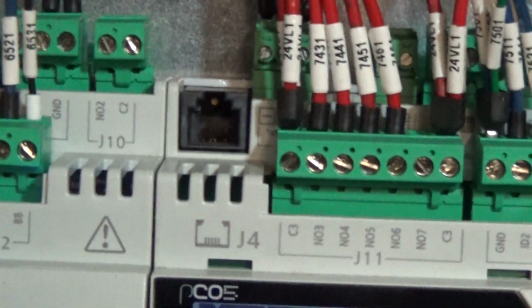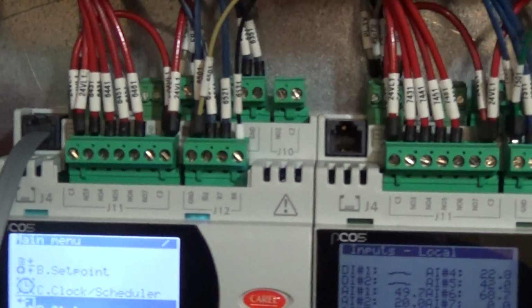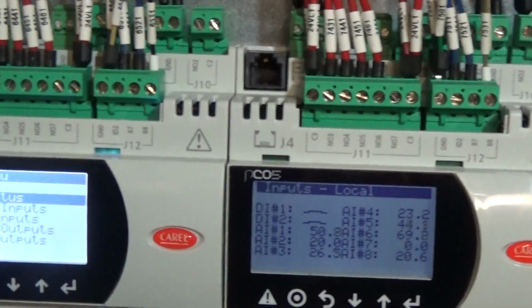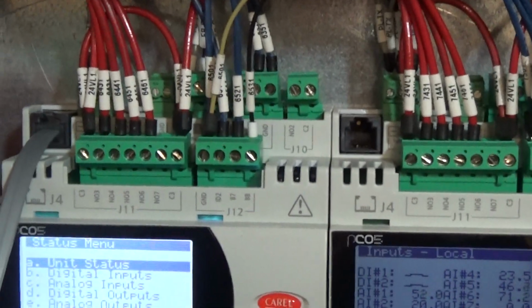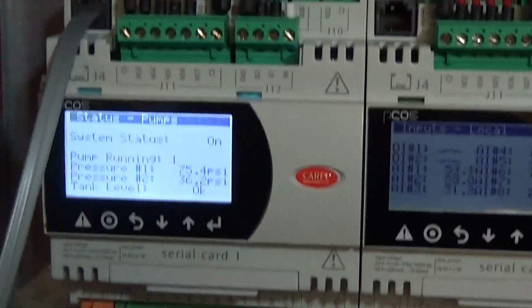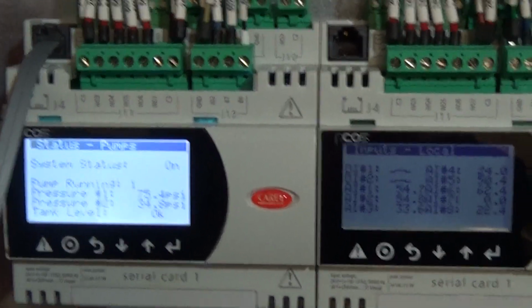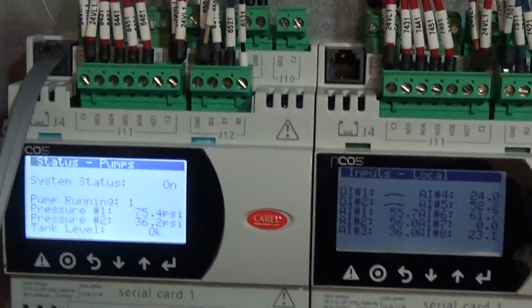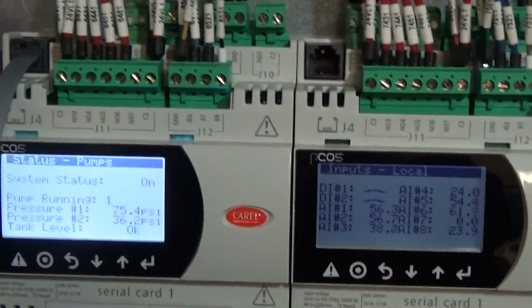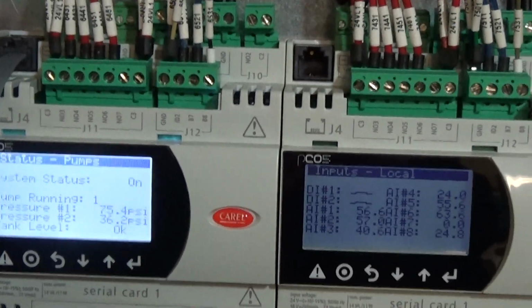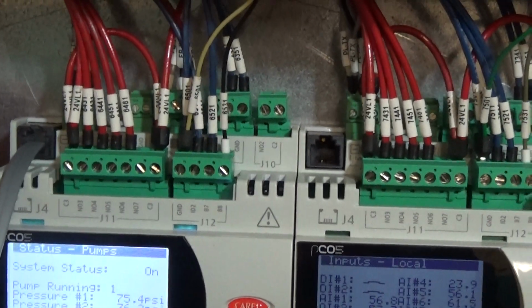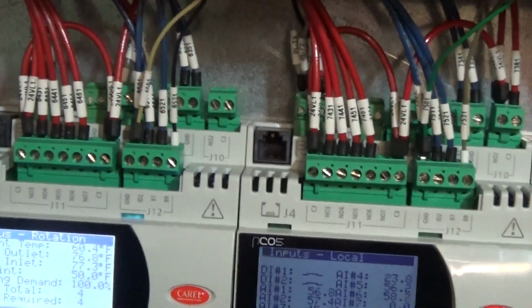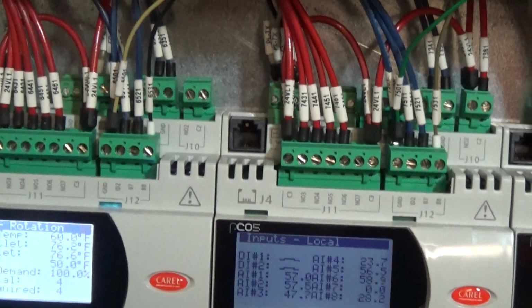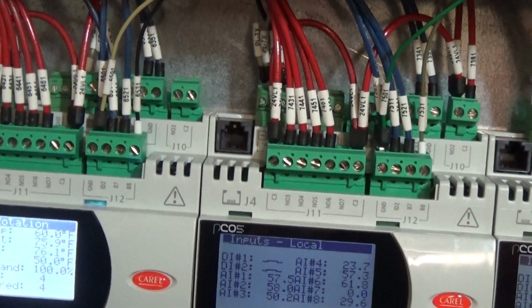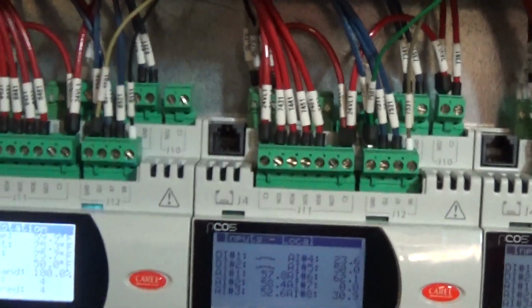And the nice thing about the PLC here is it gives me a status screen that I can read the different fluid pressures and refrigerant pressures and temperatures in the whole machine. So I'm in the status menu, I'm highlighted on unit status, I can hit enter. And what it shows me is pump 1 is running. The pressure on the flow control valve inlet is 75 psi, and the transducer on the other side is sensing 36 psi. Tank level says okay. Now that tells me ambient temperature, fluid temp in, fluid temp out, what my set point is, my demand, how many compressors are energized, and how many should be energized.